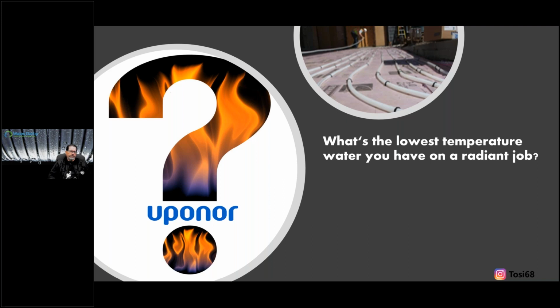Here's a question for everybody: if you would never think of lowering water temperature before, why is it okay with radiant? Why is lowering water temperature okay there? Think about that - it's surface area. The amount of surface area in the floor, 9 inches on center, 6 inches on center, commercial, 12 inches on center, 24 - it's all based on what the load is, the BTUs per square foot of the space. I can now lower water temperature. The other reason is too hot of a floor can be very uncomfortable.